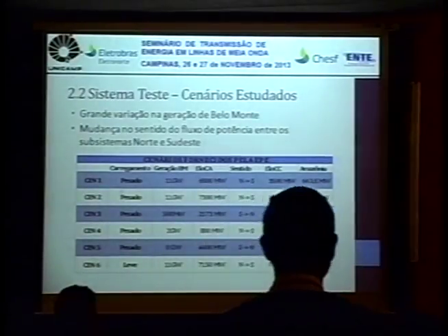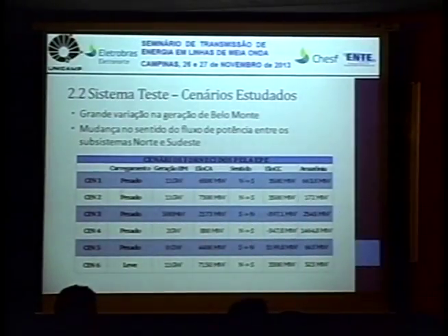So here we have several operating scenarios. Some very extreme ones, so we can verify if the half wavelength operation under these extreme conditions would be reasonable or not. This EPE report shows, for some scenarios, especially for the ones with little load on the AC link, where the efficiency is around 50, 40, or maybe 60%.